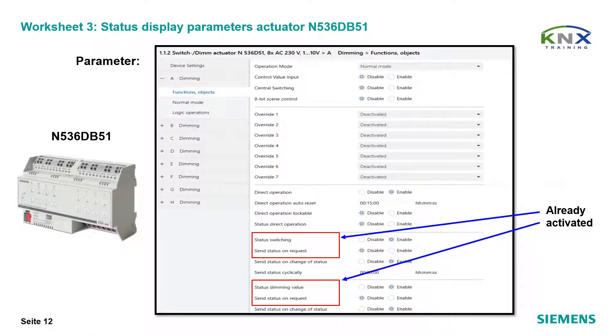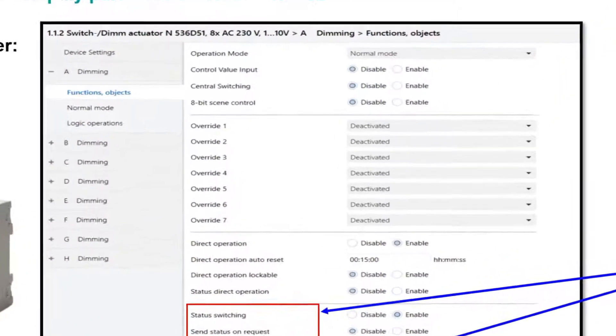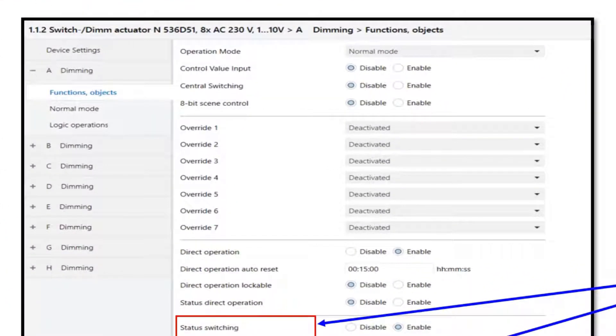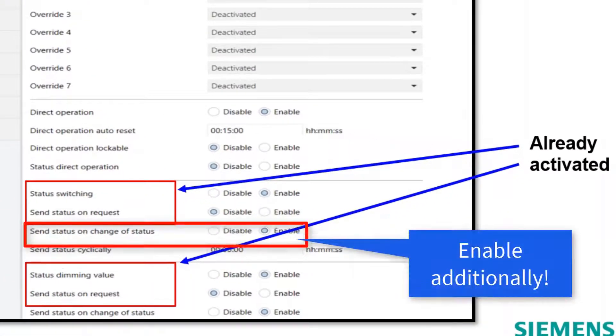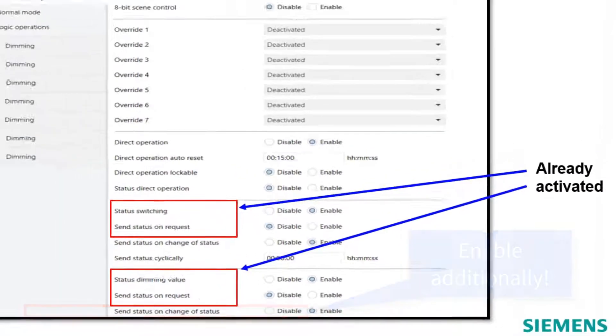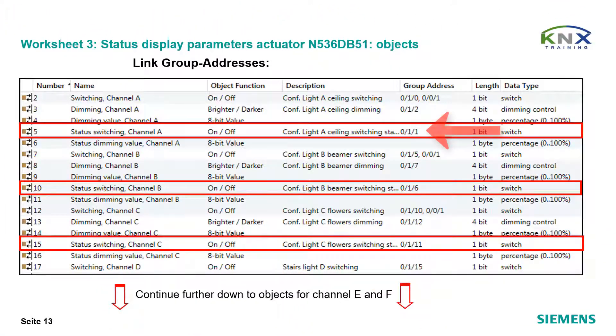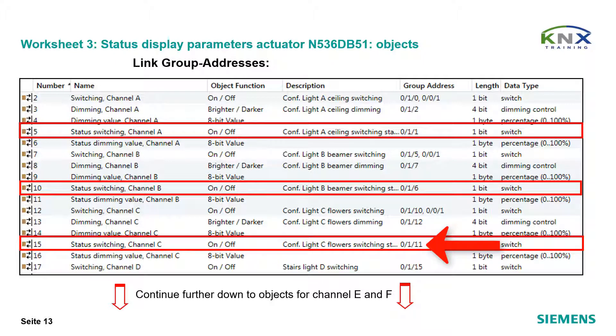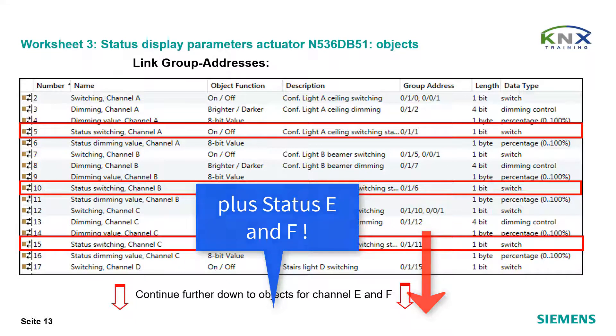Status display parameters — actuator N536DB51. Check if the actuator for switching and dimming is enabled to send feedbacks automatically on change; you must do this on the parameter page 'Functions Objects'. Check the status objects of the actuator N536DB51, create group addresses if not already created, and link them to these status objects. Afterwards, don't forget to download.